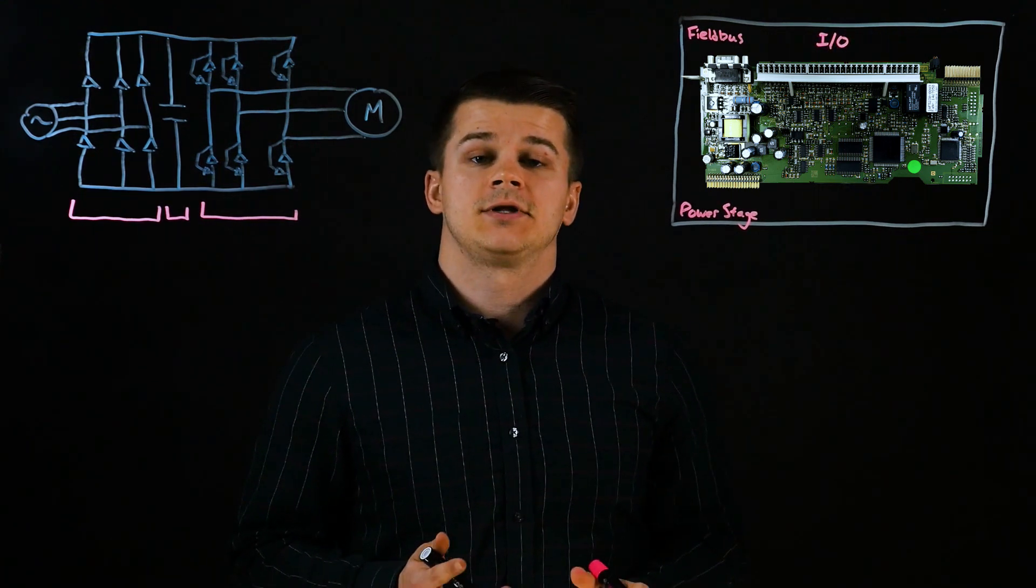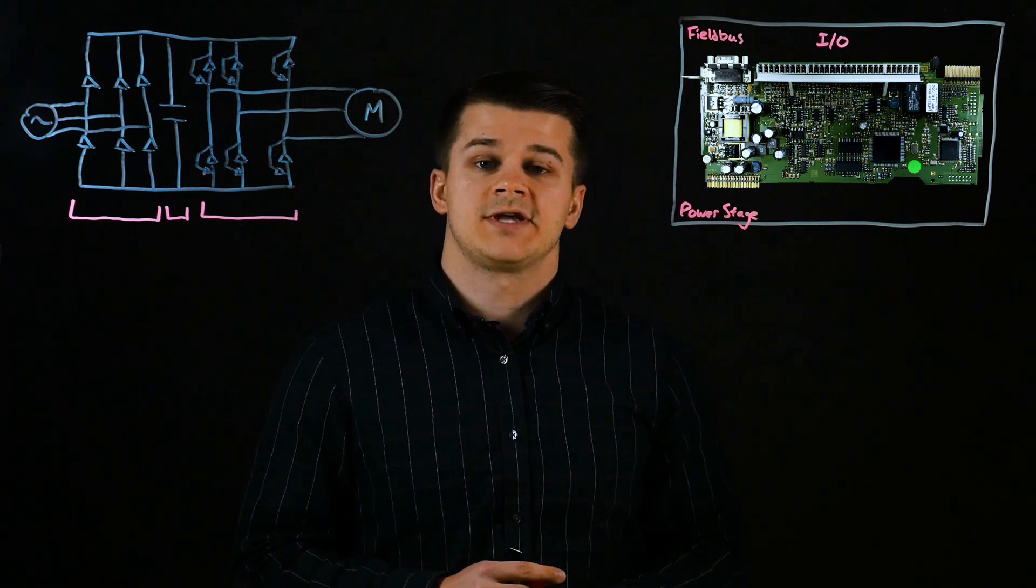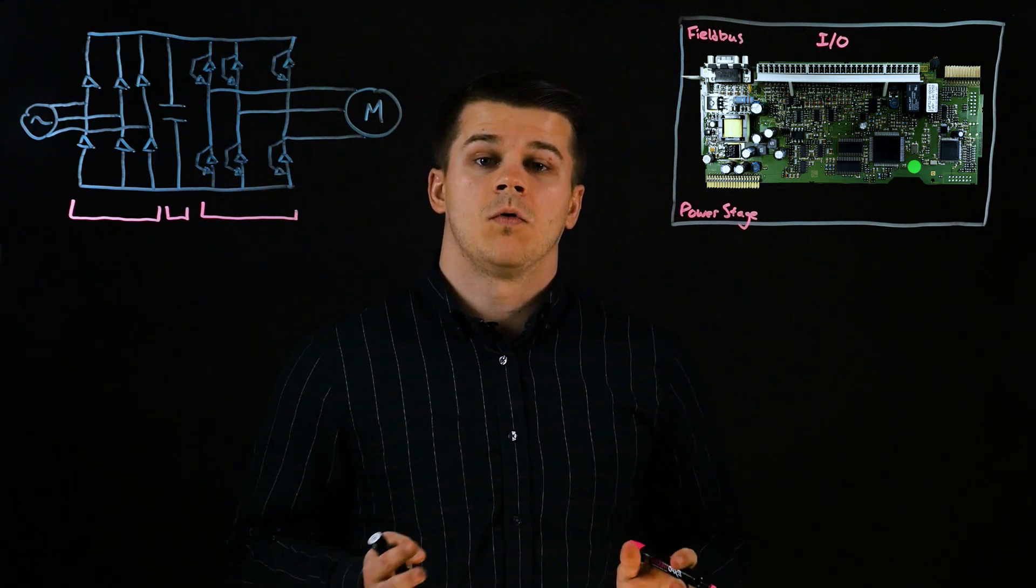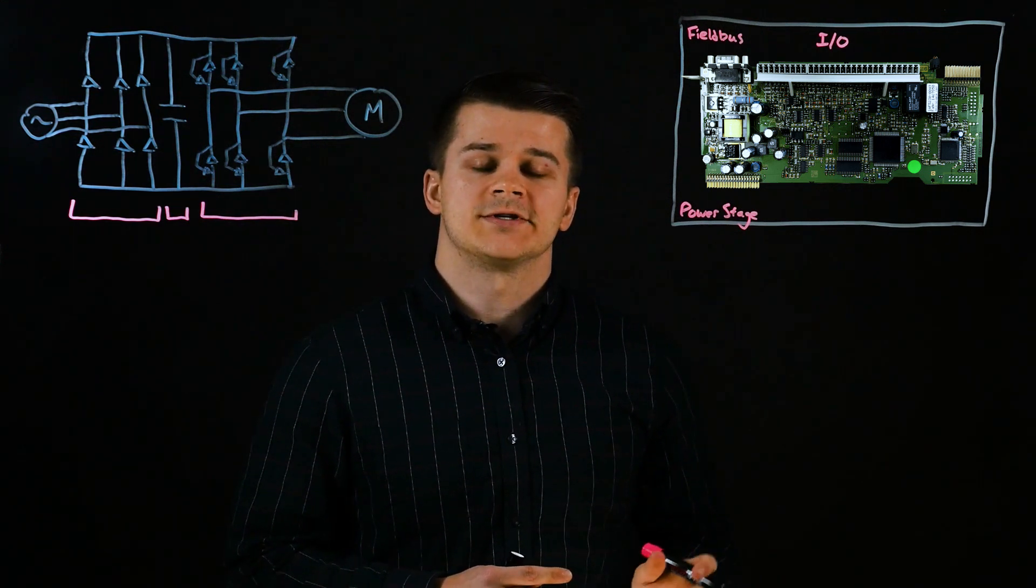Next are the analog and digital I/O. These are used for simple logic based controls. For example, the analog input can take a 0 to 10 volt signal to set the command speed. Or a digital output could signal to the rest of the machine that the motor is at its command speed.